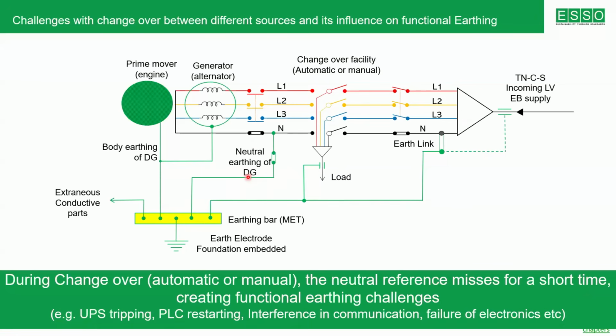In several places, a lot of people have this particular challenge. That means once when the mains is off, then immediately you have the generator, but there is a changeover. But during this particular time, some of the electronic equipment are not working. Now, in order to ensure safety of that particular equipment, let's say a UPS manufacturer, the UPS is using incoming neutral as the reference of the electronic equipment in the UPS.